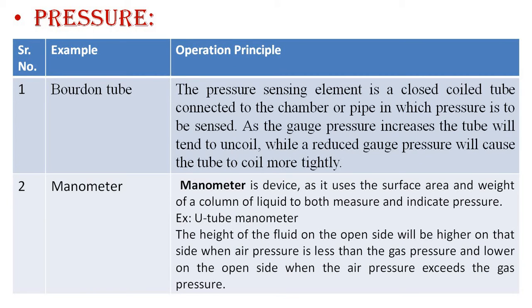The second parameter is pressure. We use different types of sensors to measure pressure. Starting with the Bourdon tube: it senses pressure and gives the desired output in terms of displacement. The pressure-sensing element is a closed coiled tube connected to the chamber in which pressure is to be sensed. As gauge pressure increases, the tube tends to uncoil, and reduced gauge pressure causes the tube to coil more tightly.